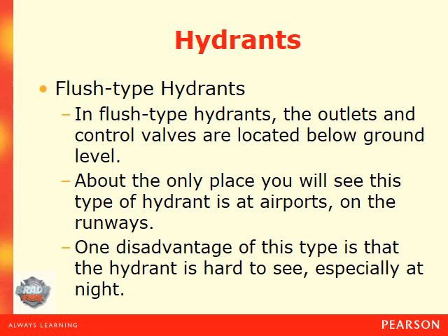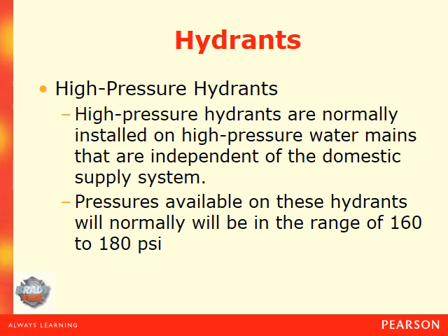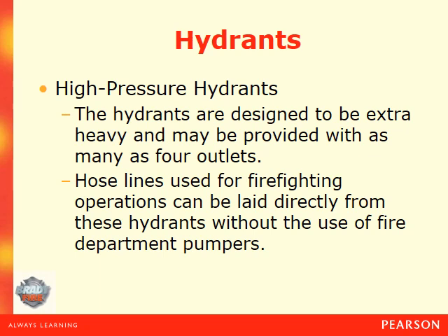In flush type hydrants, the outlets and control valves are located below ground level. About the only place you will see this type of hydrant is at airports on the runway. One disadvantage is that the hydrant is hard to see, especially at night. High pressure hydrants are normally installed on high pressure water mains that are independent of the domestic supply system; pressures on these hydrants will normally range between 160 and 180 PSI. These hydrants are designed to be extra heavy and may have as many as four outlets. Hose lines for firefighting can be laid directly to these hydrants without fire department pumpers to boost the pressure.